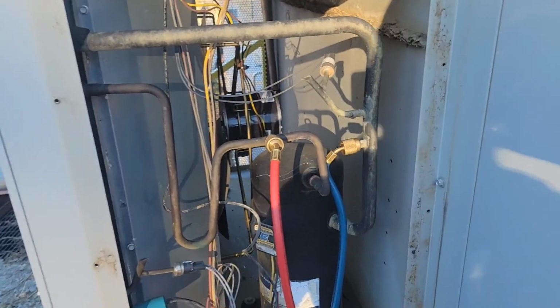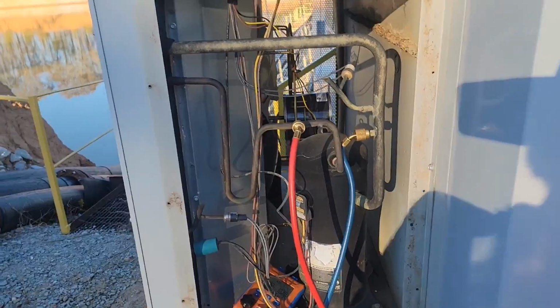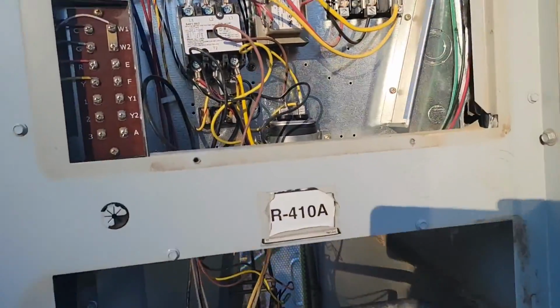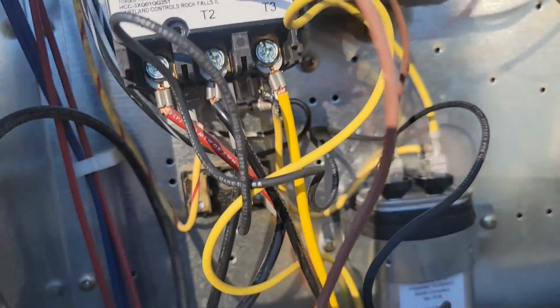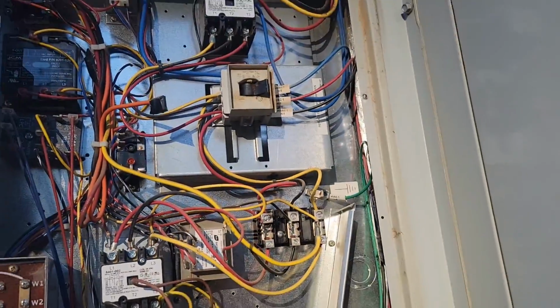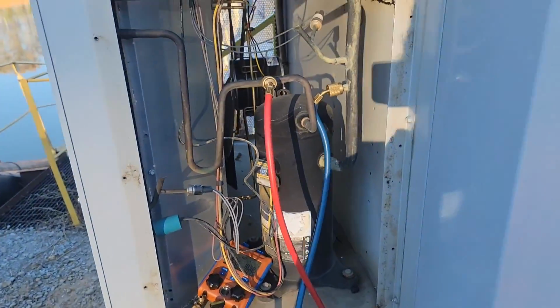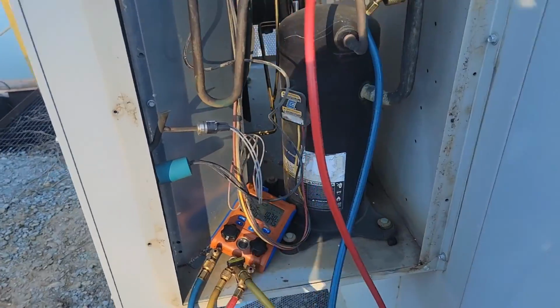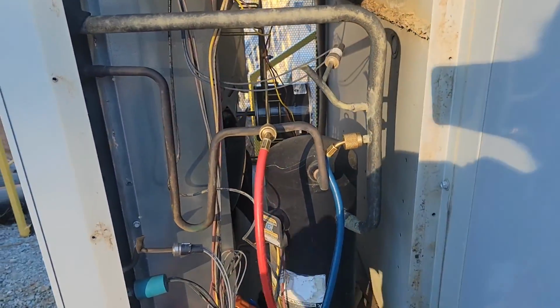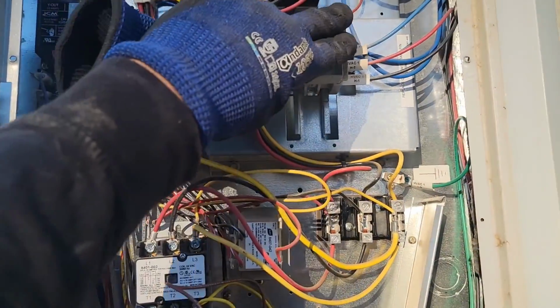Moment of truth, got the gauges hooked up because I want to measure the pressures, make sure the head pressure's not too high. But moment of truth here, you can see how it's wired. Did I make a wrong decision by changing that motor? Is that high pressure switch the problem? Is the motor bad? Let's see.